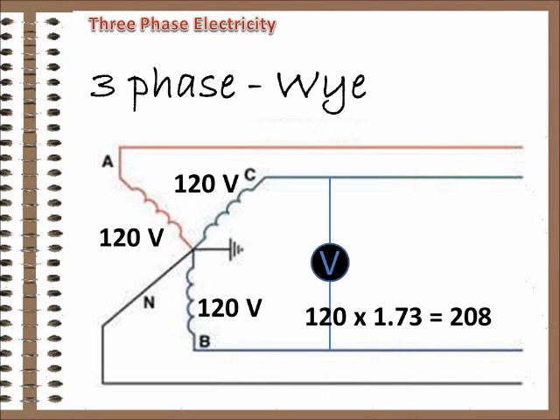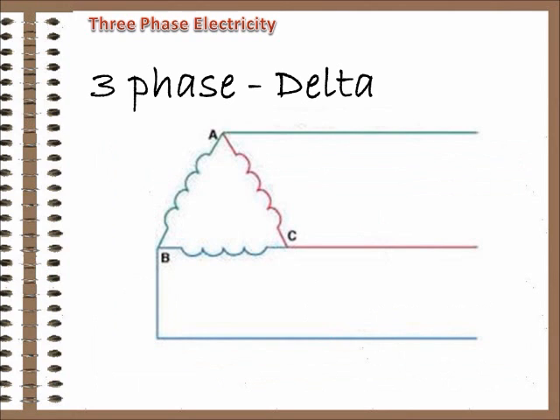The math works out to 1.73 times the voltage in one phase. So, connecting the three phases this way, Y, gives us 120, 208 service, or any proportional pairing, depending on the transformer ratio.